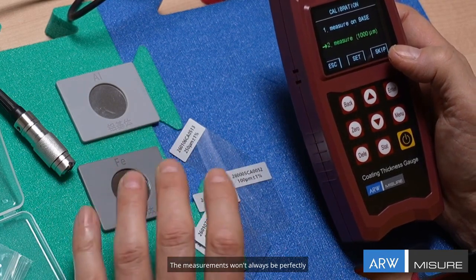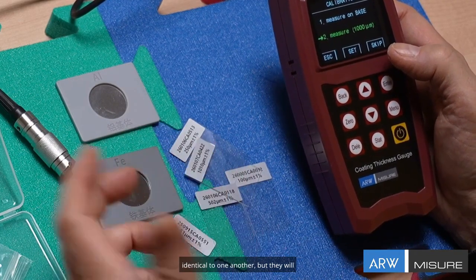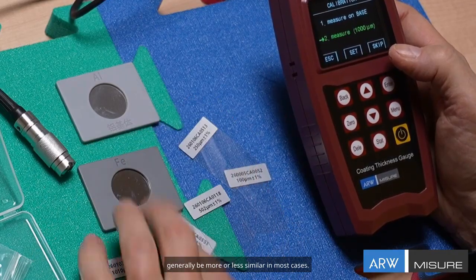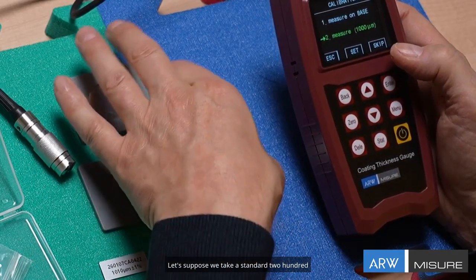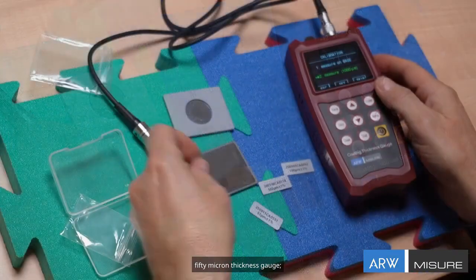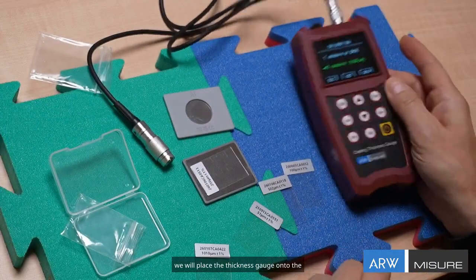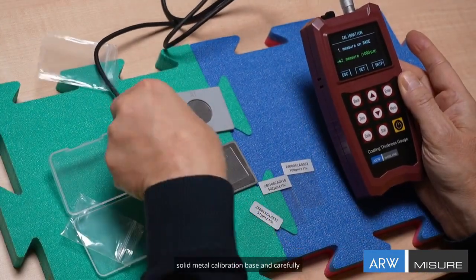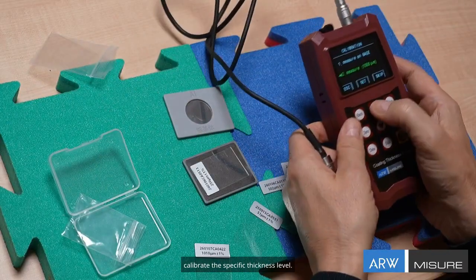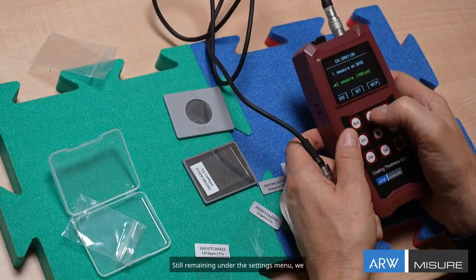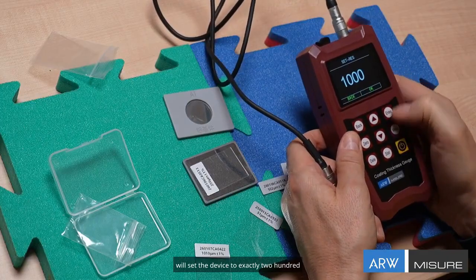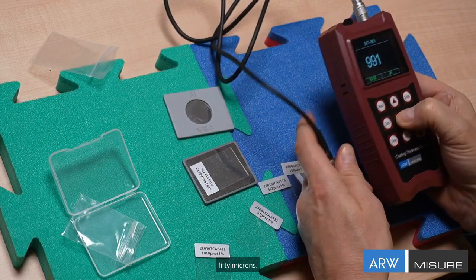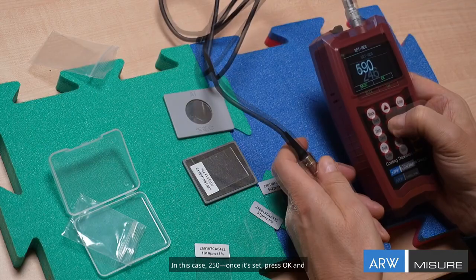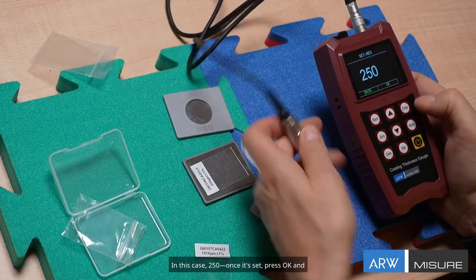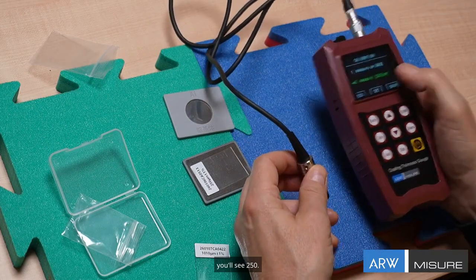The measurements won't always be perfectly identical to one another, but they will generally be more or less similar in most cases. Let's suppose we take a standard 250 micron thickness gauge. We will place the thickness gauge onto the solid metal calibration base and carefully calibrate the specific thickness level. Still remaining under the settings menu, we will set the device to exactly 250 microns. In this case, 250. Once it's set, press OK and you'll see 250.